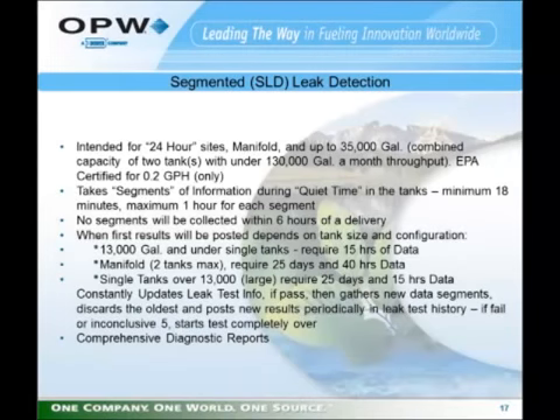Segmented leak detection is intended for sites that are deemed 24-hour sites or are pumping day and night and do not close. It is certified for a manifold group of up to 2 tanks, a total capacity between the 2 tanks of 35,000 gallons, and a total throughput per month of the manifold group or the single tank of less than 130,000 gallons. It is certified as a 0.2 gallon per hour test only.